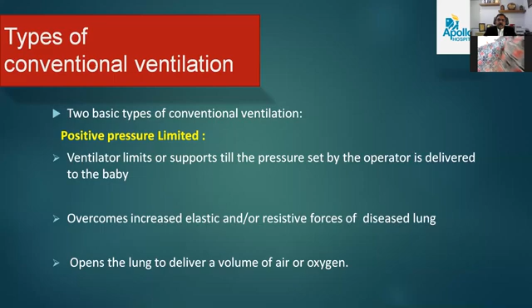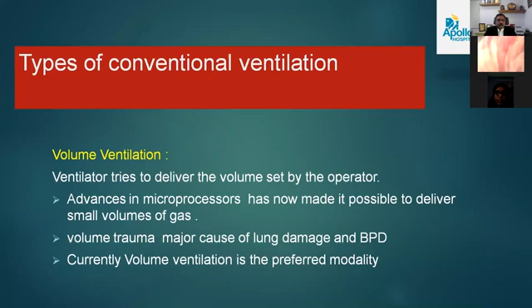The second mode, which has come over the past decade or so, is volume ventilation, which is gaining a lot of ground and has enough evidence that volume ventilation is the way forward. The ventilator tries to deliver the volume set by the operator. Advances in the microprocessor make it possible to deliver even very small, minute amounts of gas volume. Volume trauma, which is a major cause of lung damage, can be prevented. Currently, as I said, volume ventilation is the preferred modality.